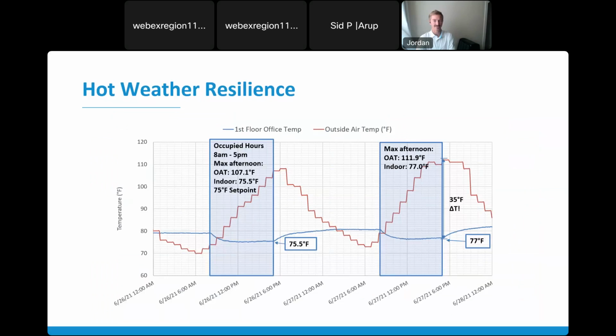System got tested. We hit 112. We had that heat dome effect that very summer. The building crushed it, even at cutting the system capacity in half. With outside air temperatures 20 degrees over our design cooling condition, we were still able to maintain a comfortable space temperature. And this is, people often run their HVAC units 24/7 in extreme conditions.